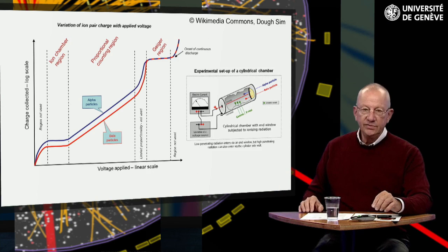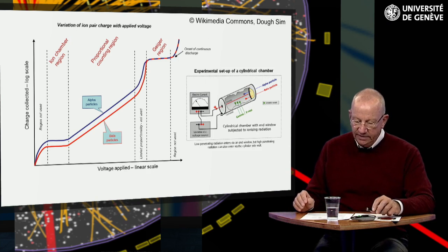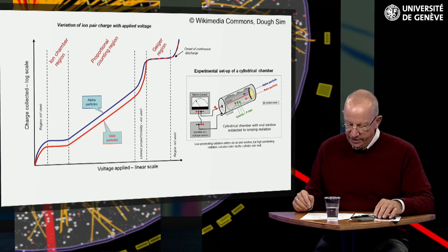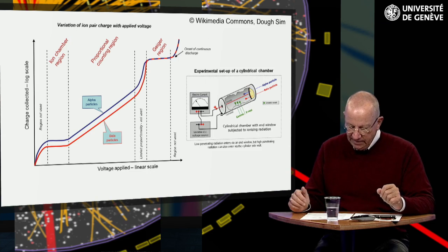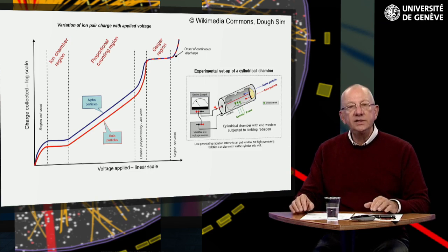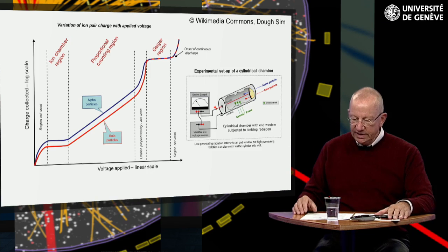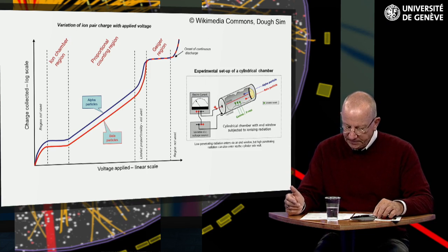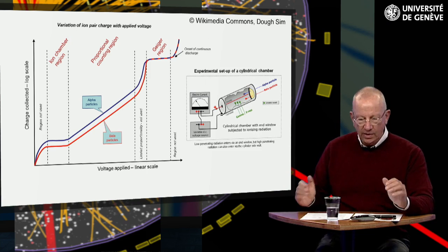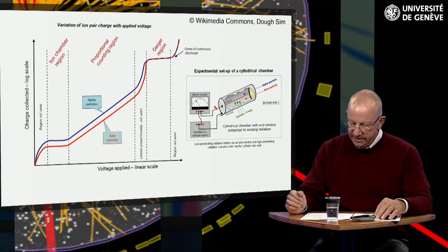The advantage of using this region is that low radiation levels can be measured by counting particle rate, even if the particles have low energy. The disadvantage is that the energy of the particles cannot be measured. The discharge stops when the space charge formed by the positive ions around the anode decreases the electric field sufficiently so that the avalanche process stops. The detector will be insensitive to new ionization until the positive ions have migrated far enough from the anode. This is the origin of dead time in a Geiger counter.